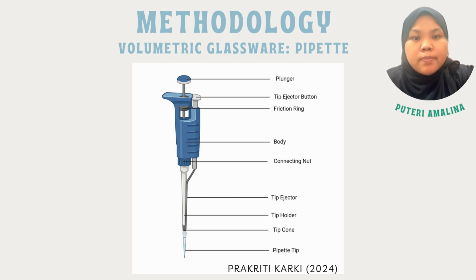First, the plunger. The plunger is used to aspirate and dispense the desired volume of liquid. Number 2, the tip ejector button is to eject the used pipette tips. Third, the volume window displays the set volume, and the place values shown depend on the pipette size. Fourth, the tip cone is where the tip is attached. And lastly, the pipette tip is a piece of equipment made of polypropylene that has been molded and comes in contact with the liquid. Remember, the pipette tips must always be sterile before use.